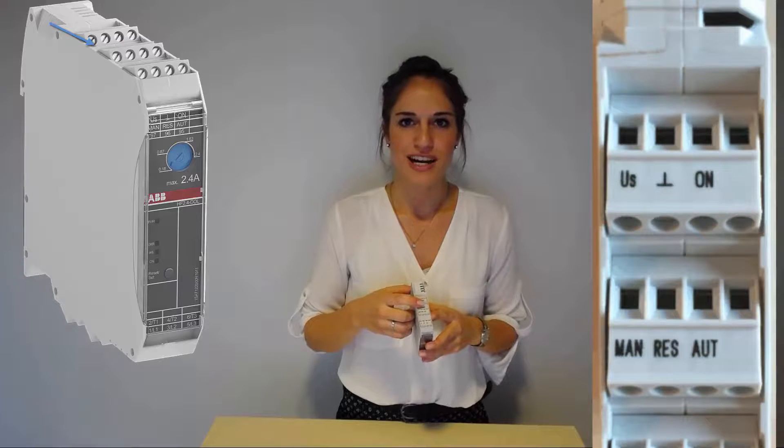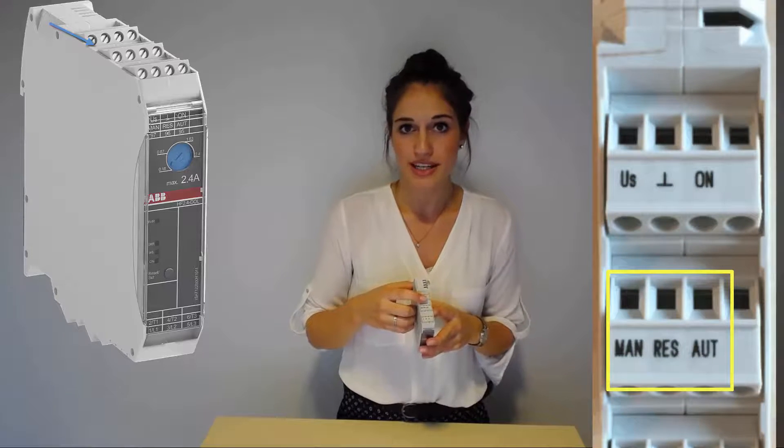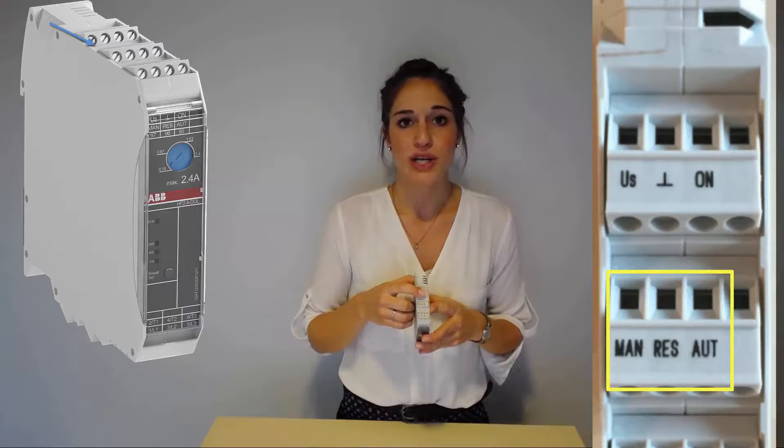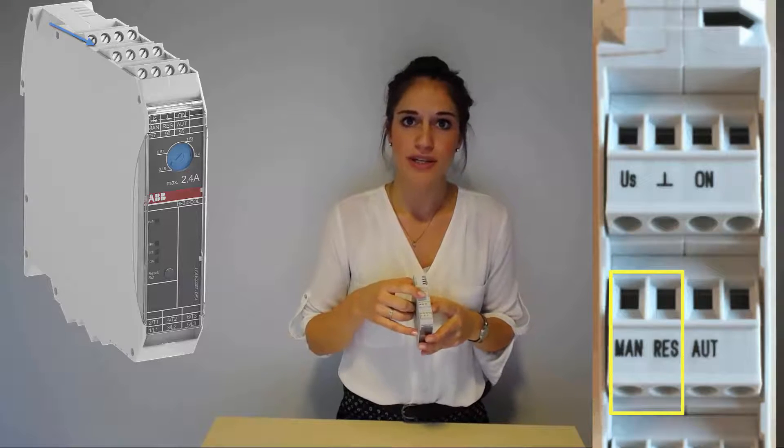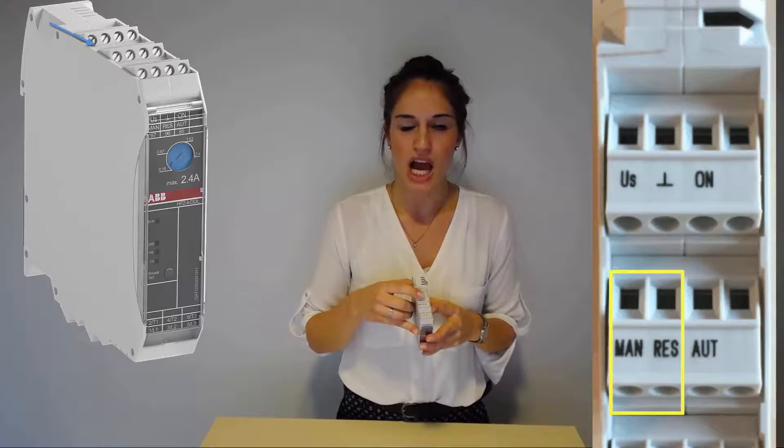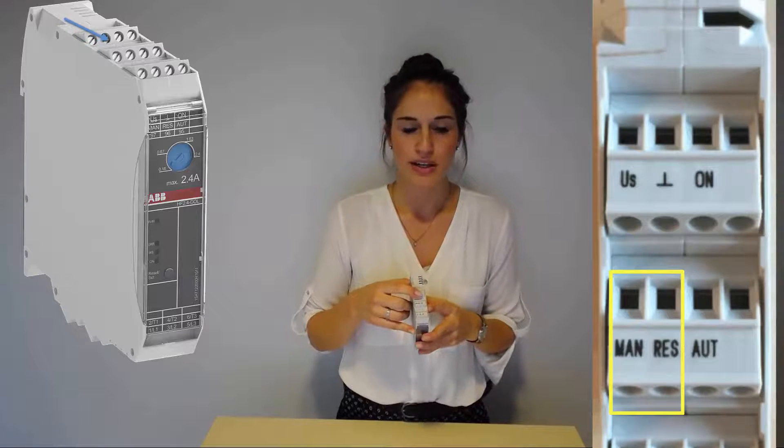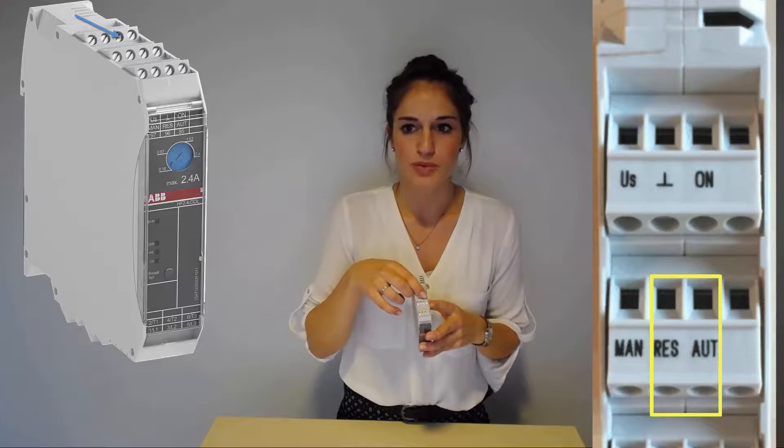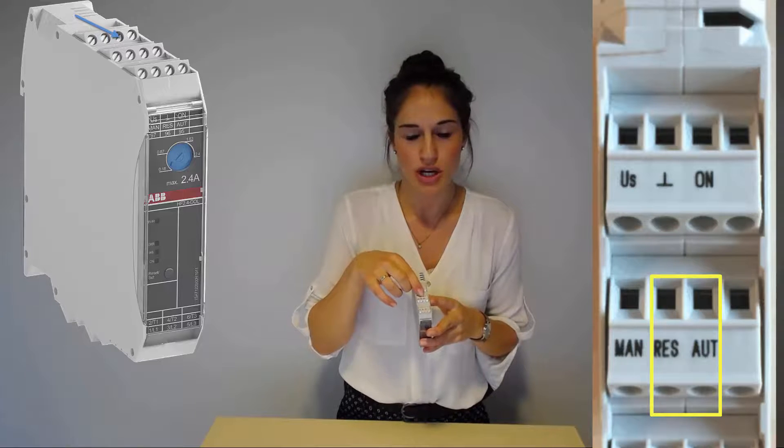After the overload function has tripped, the HF range can be reset automatically or manually. For manual reset, connect the push button with a normally open contact between the MAN and the RES terminals. For automatic reset, establish an electrical connection between the RES and AUT terminals.